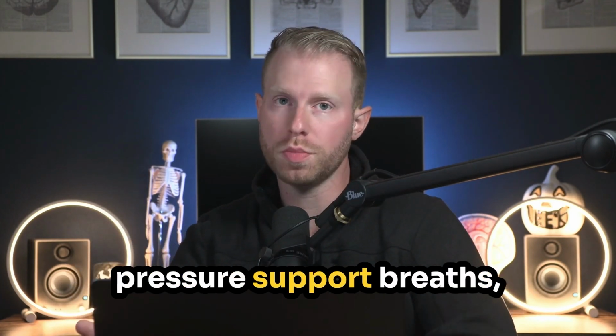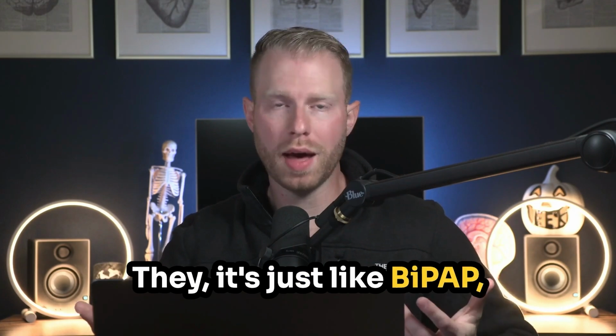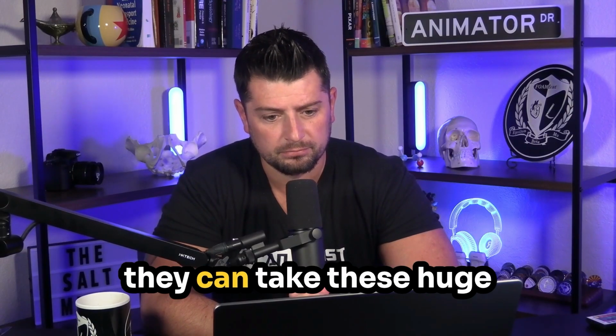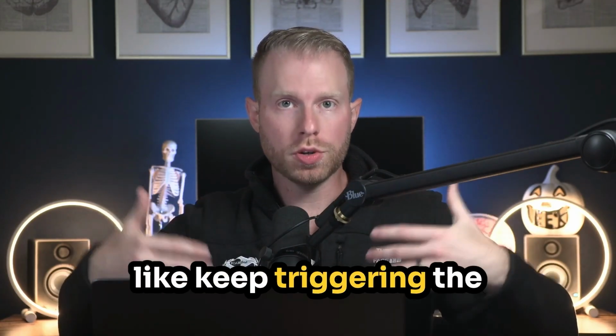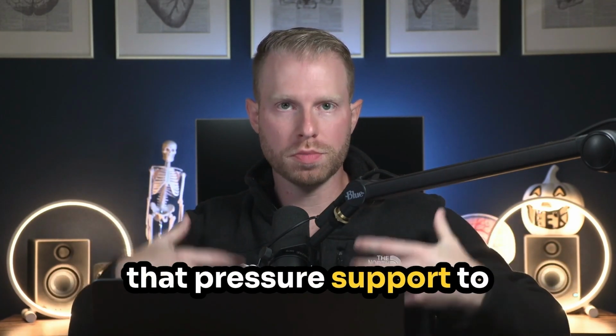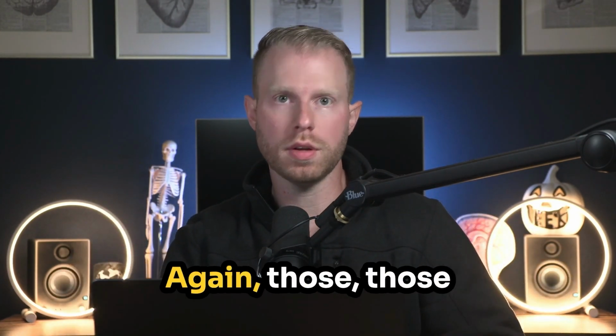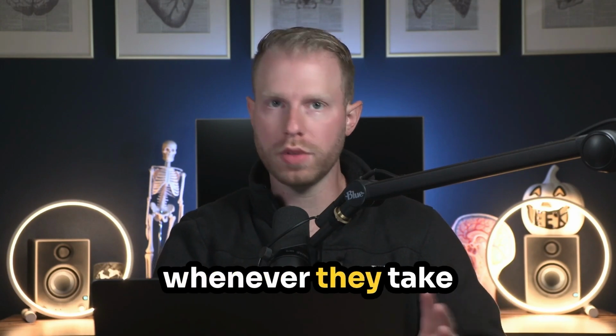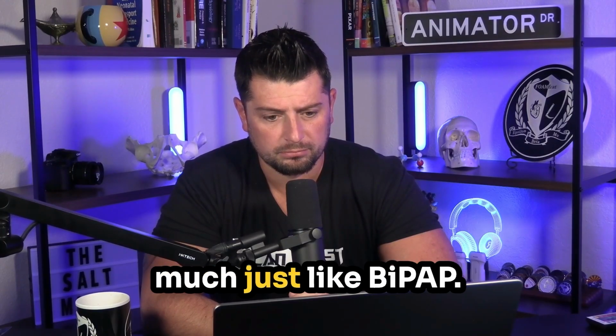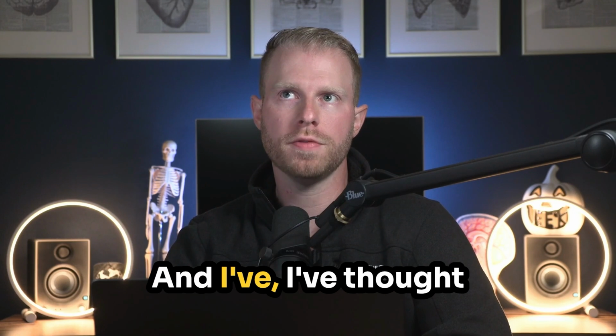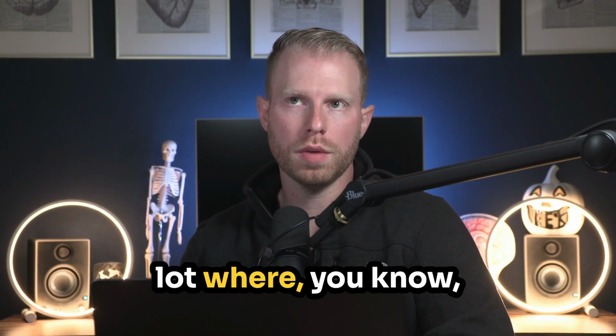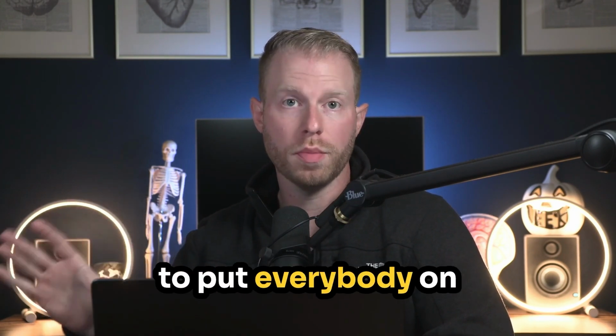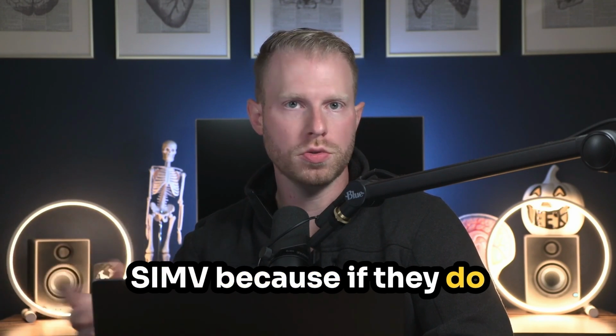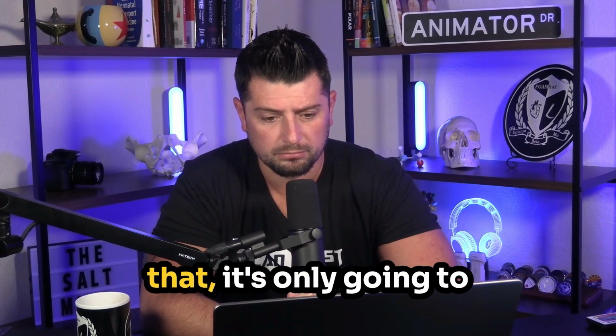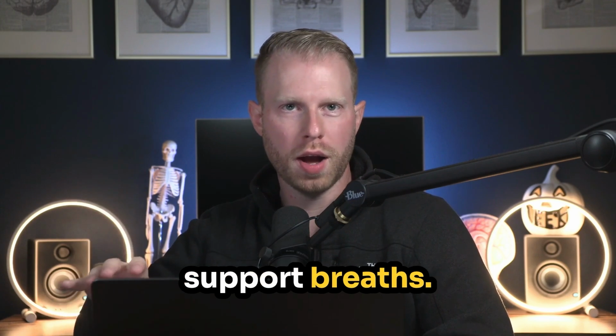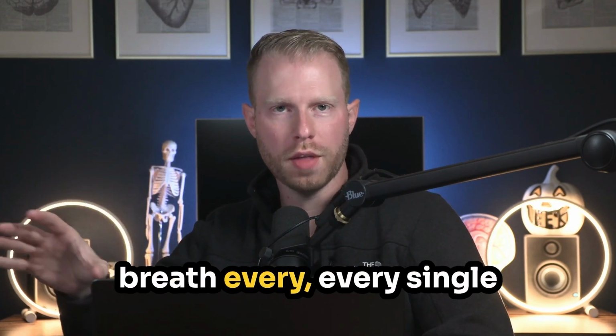Whereas with those pressure support breaths, it's just like BiPAP. When somebody's on BiPAP, they can take these huge breaths and they can just keep triggering the vent, and it keeps adding that pressure support to them as they breathe in. Again, those SIMV breaths, whenever they take a spontaneous one, it's going to be pretty much just like BiPAP. And I've thought about that problem a lot where some people will be like, I'm just going to put everybody on SIMV because if they do start to auto trigger or something like that, it's only going to be these pressure support breaths, and it's not going to hammer them with the full breath every single time this thing cycles.